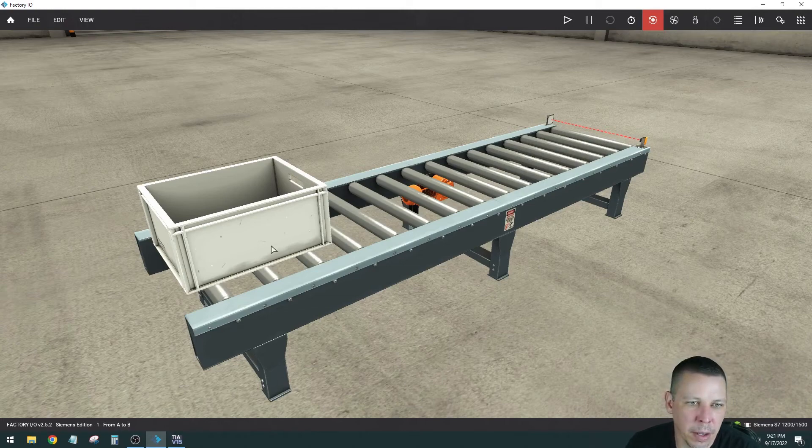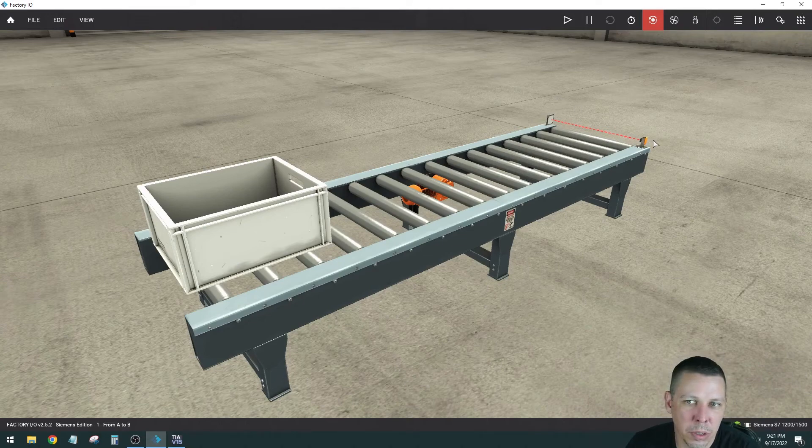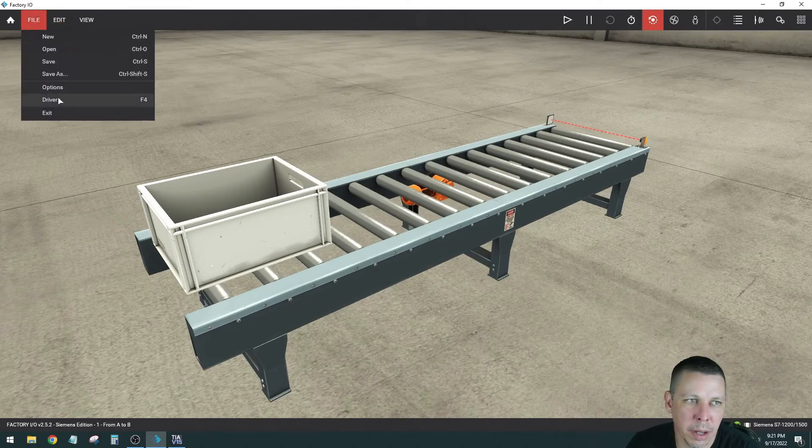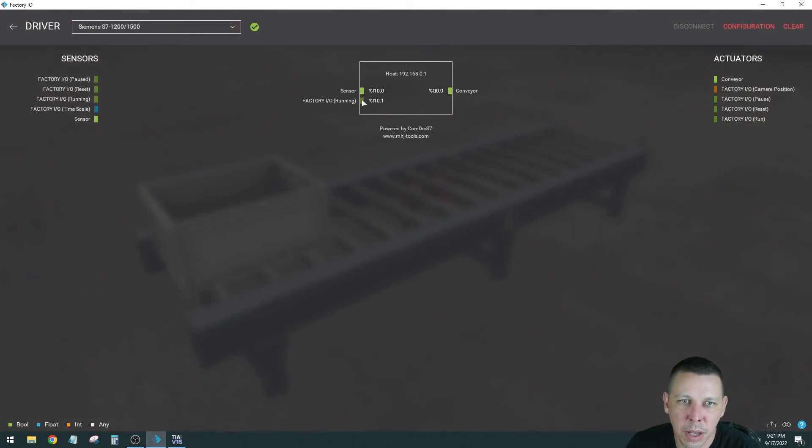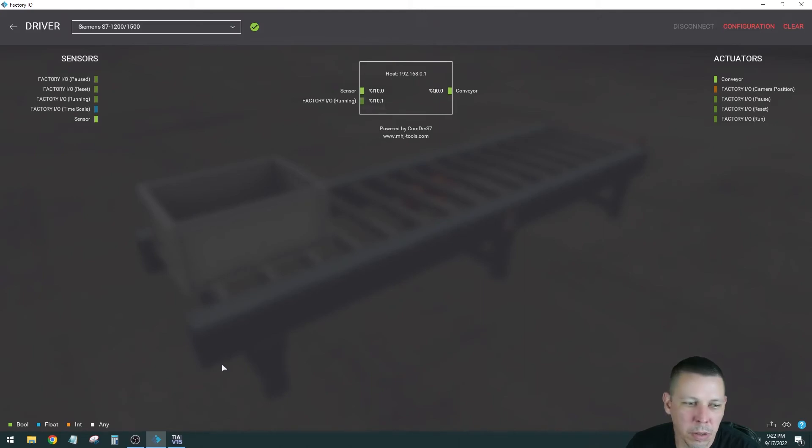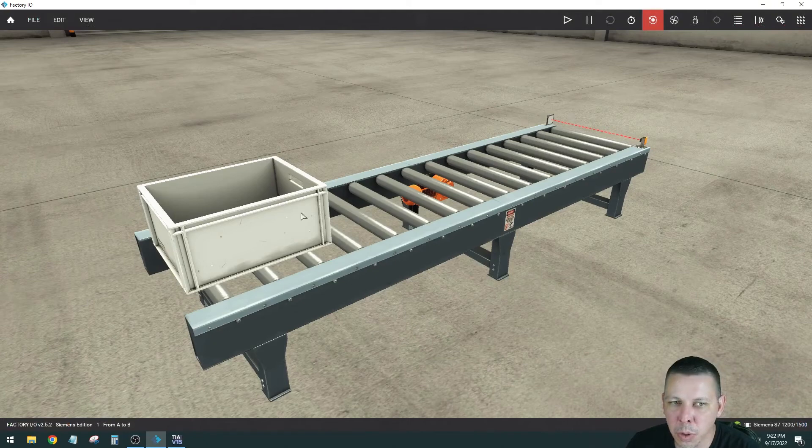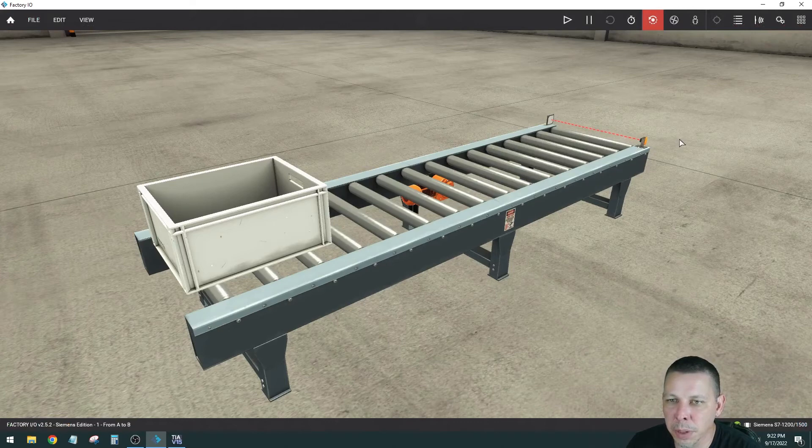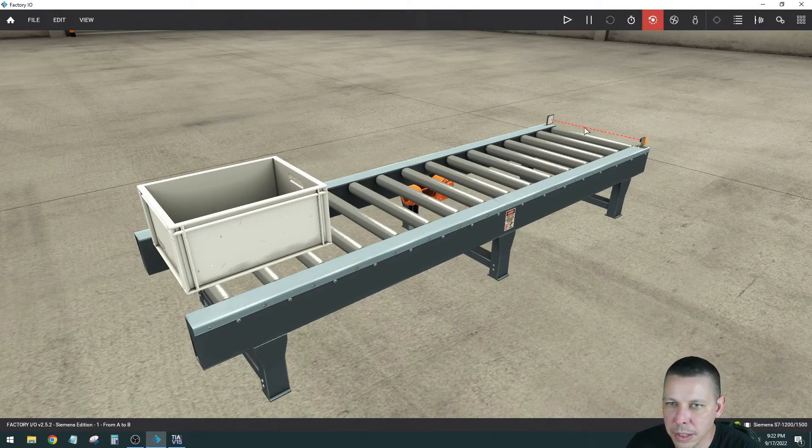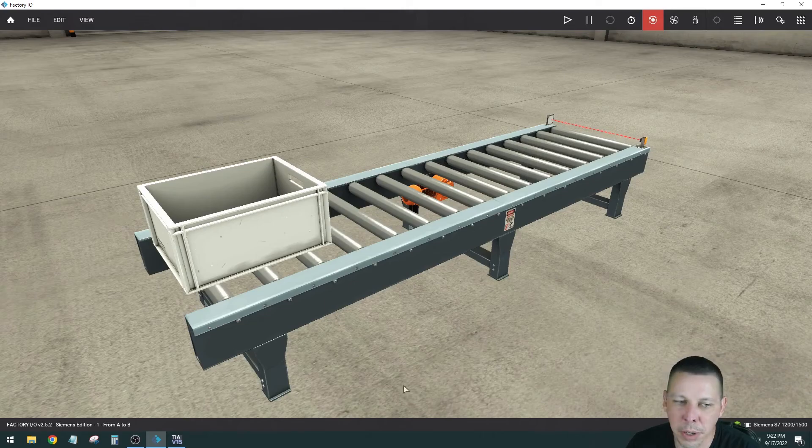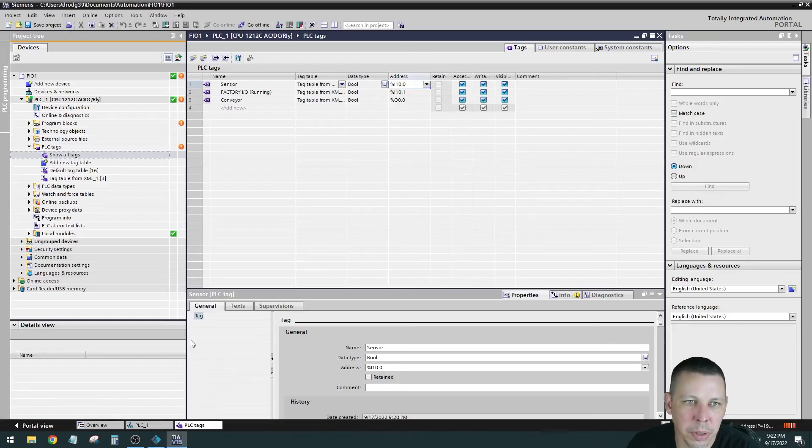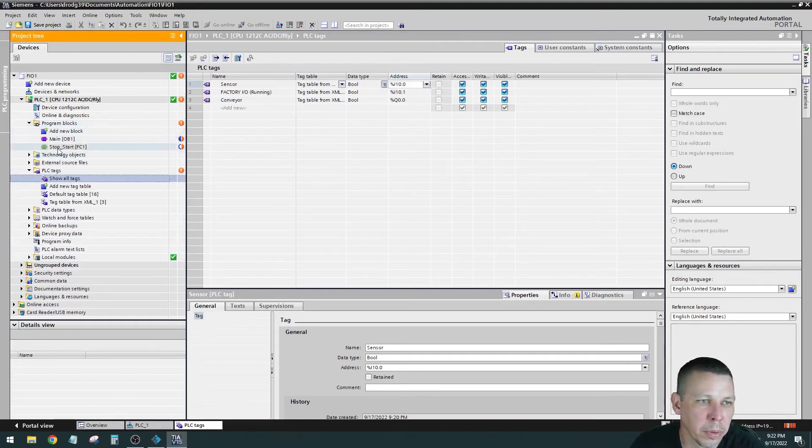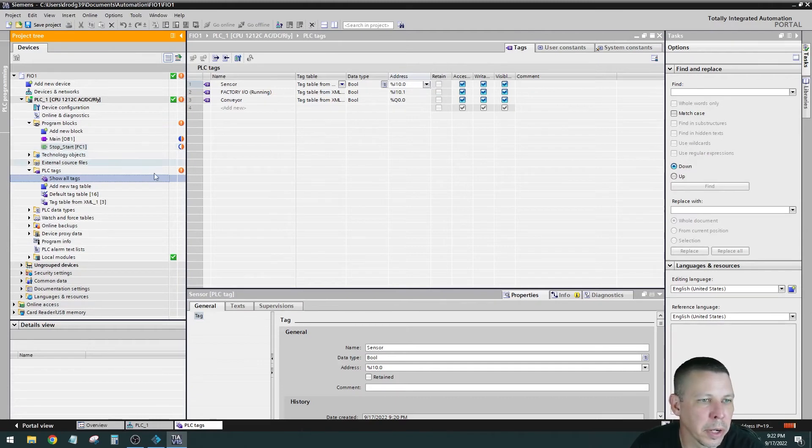So what do we have now? We have the conveyor that's going to be running unless the sensor is made. So the first thing I want to check is, is the sensor outputting right now or not? If you go to drivers, if it's dark, it's false. If it's lit up, it's true. So this is lit up. So that tells me that I want to put a normally open for that sensor. I want this thing to run until the sensor is broken by the box. So it's sending out a signal right now. So if I use a normally open contact, it'll be closed until this thing gets there and then it'll break it.